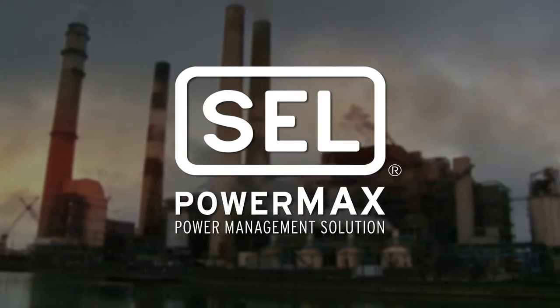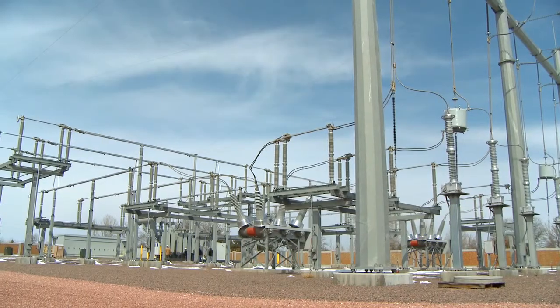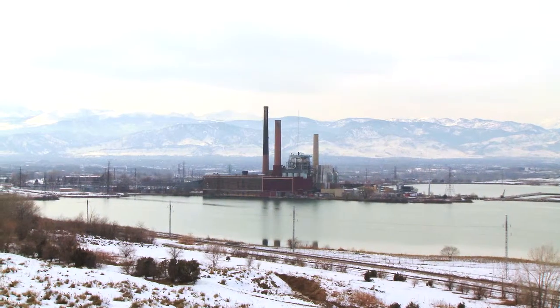The SEL PowerMax system is our industrial power management system and utility special protection scheme. It can include a suite of functions such as SCADA, event retrieval, breaker monitoring, a complete protective relaying system, a complete control system for their electrical grid, and a complete blackout mitigation and remediation system such as load shedding, generation shedding, and proactive schemes more along the lines of a modern generation control scheme.